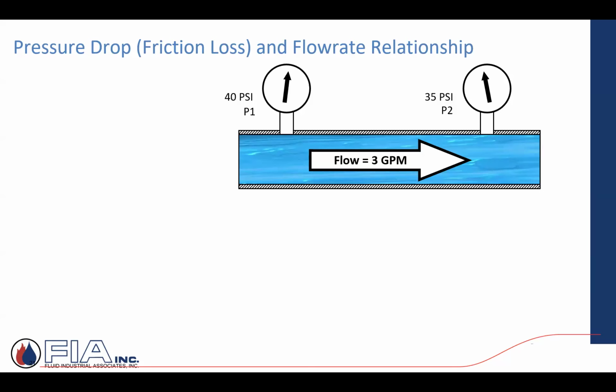So now you're kind of jumping right in. We're saying, okay, I got this system. It's pumping 3 gallons a minute through a coil, a hydronic coil, chilled water, whatever the case may be. And I have gauges on the inlet and the outlet, and they're reflecting a 5-pound pressure drop. It's coming in at 40 and exiting that particular coil 5 pounds lower at 35 PSI at a flow rate of 3 gallons a minute.